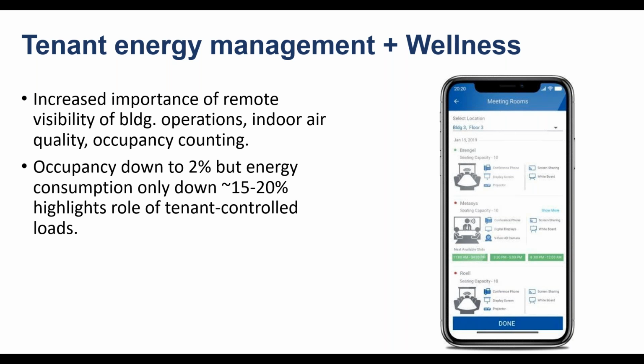It's really important, from a whole building energy and carbon reduction standpoint, to get a better hold on phantom loads in tenant spaces. This was highlighted well when occupancy levels in New York City buildings dropped to 0 or 2%, but energy consumption dropped only about 15 to 20% on average. A lot of building operators didn't know what was driving loads in these unoccupied spaces, because nothing in the leased spaces was visible to the building operator. So there's really a need for more remote monitoring and control of these spaces, which highlighted and cemented this hypothesis about where we should take R10 next.